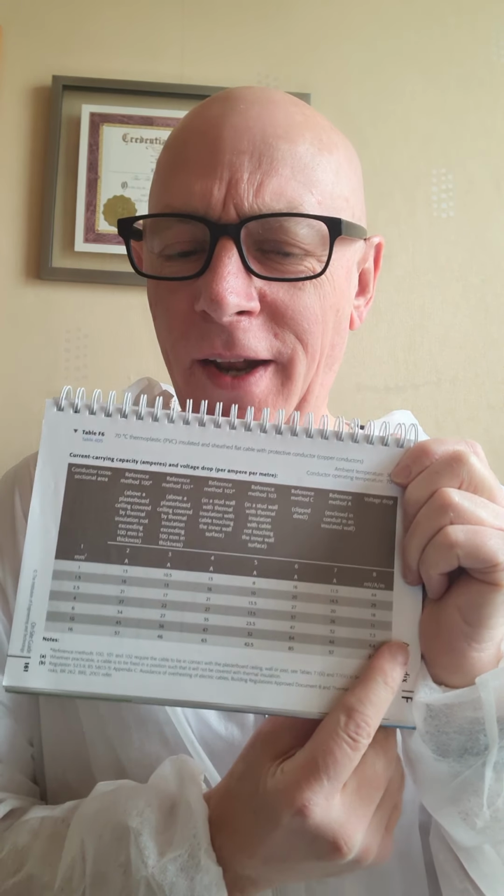And then finally, the easiest table of all, and probably the one you're most likely to be asked about in online multiple choice exams, is flat profile cable. You'll know it more commonly as twin and earth or 3-core and earth. So I like this table because it combines everything in one. It has the sizes of cables and their current carrying capacities on the left hand side, and then on the far right hand side it has the millivolt amps per metre volt drop values that you need to verify your volt drop.